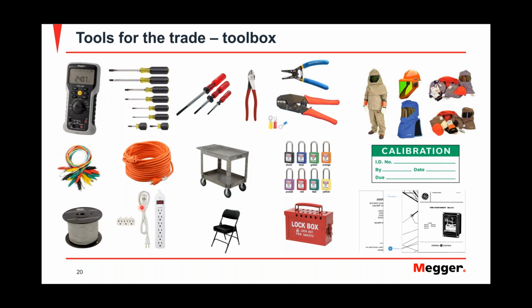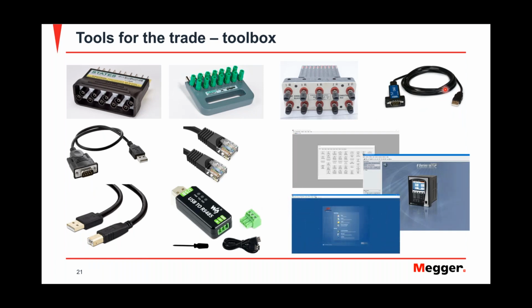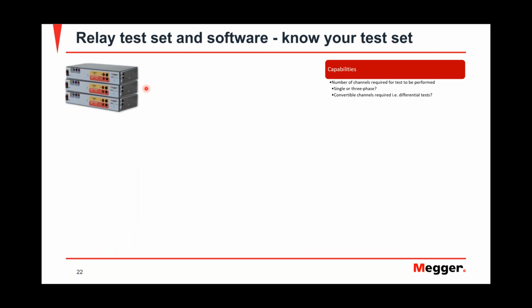Wire, some splitters, extension cords. Now, how you're connecting to the relay, there are different media that are used. Have the software that the relay uses, and test paddles. So in order to connect to your test switches, this is for a GE, this is for an ABB electromechanical relay. If you're connecting to test switches, have the one that's needed for the application. Make sure that you have what you need.